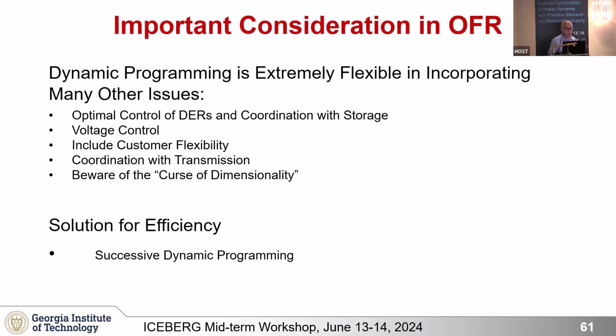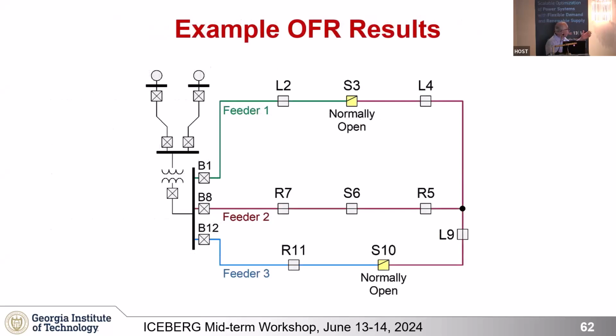For this problem we use successive linear dynamic programming, because dynamic programming is very flexible for this problem. However, the curse of dimensionality can make it really inefficient. By utilizing successive dynamic programming, focusing optimization around a band of the system's trajectory over time, we generate a highly efficient problem. Normally in the United States all feeders are operated radially—there's always a normally open switch so every feeder is a radial system—and there are many switches with different characteristics and capabilities to open and close.